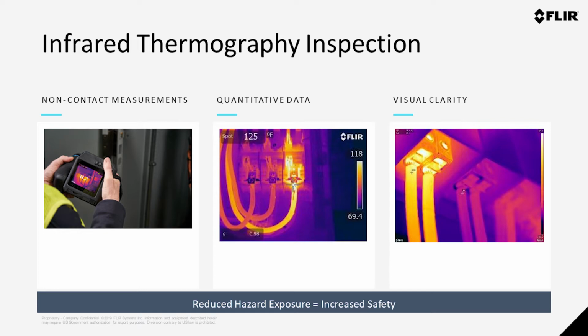The temperature range is the minimum and maximum the tool can measure. If your camera has a maximum range of 650 degrees Fahrenheit, but you're trying to measure something at 850 degrees, you won't get accurate results.